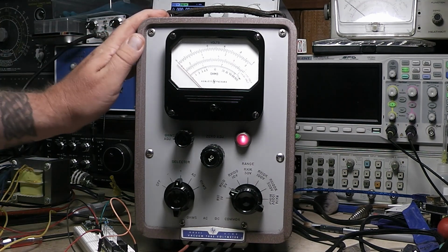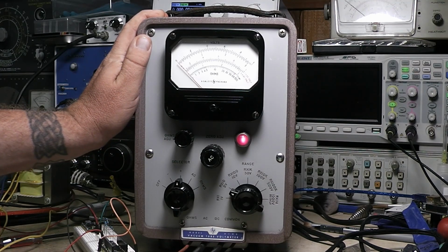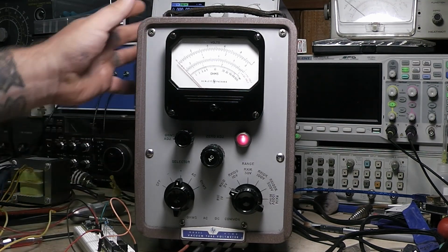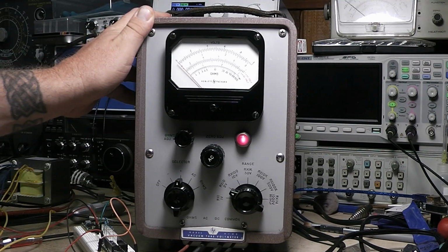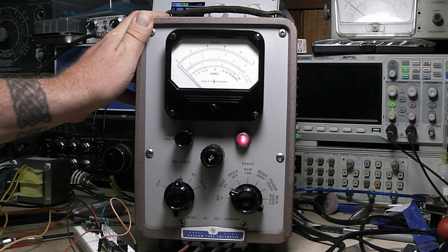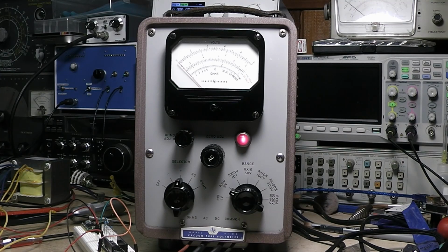If you take something like this and send it off to somebody to calibrate, these calibration places, something like this that's got a linear supply in it with a big heavy transformer, they're going to ask you what is your average line voltage at your, some people have the money at home in their home shop to say, hey, at my house, but most of the time it's a business. You got a business and you're sending your test equipment off because it costs a couple thousands of dollars to have it calibrated. And they're going to ask you what is your average line voltage. And they're going to set their variacs and isolation transformer variac setups to what you tell them, and that's what they're going to calibrate it at.